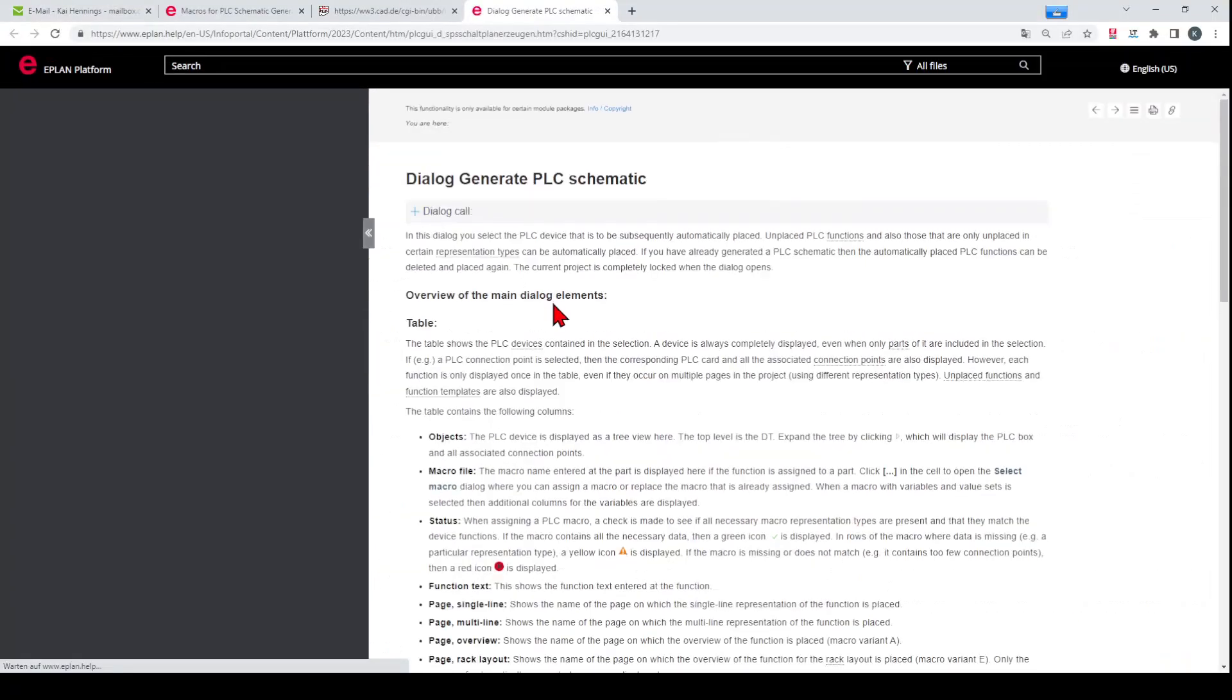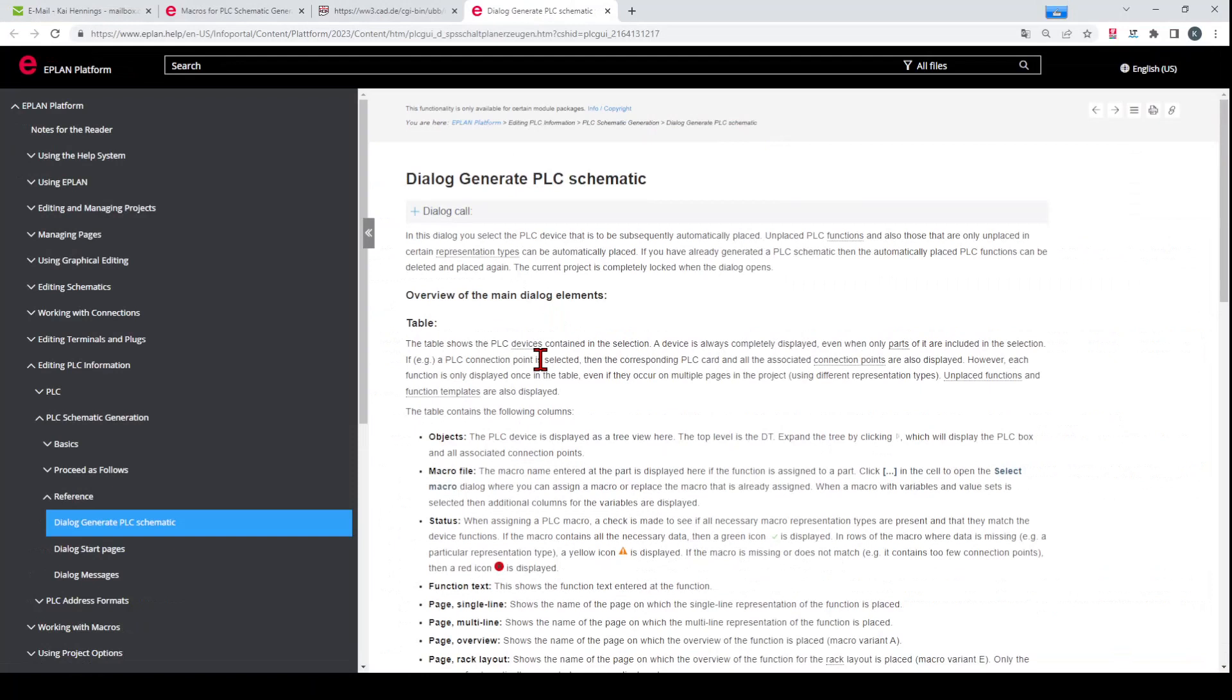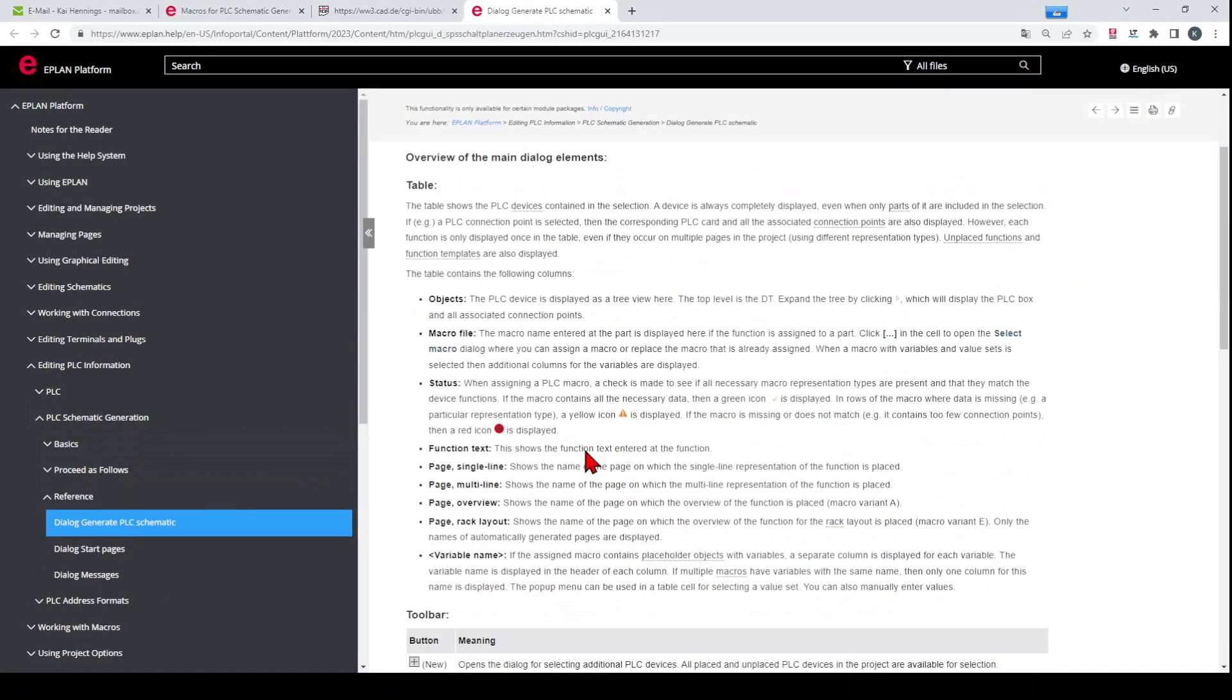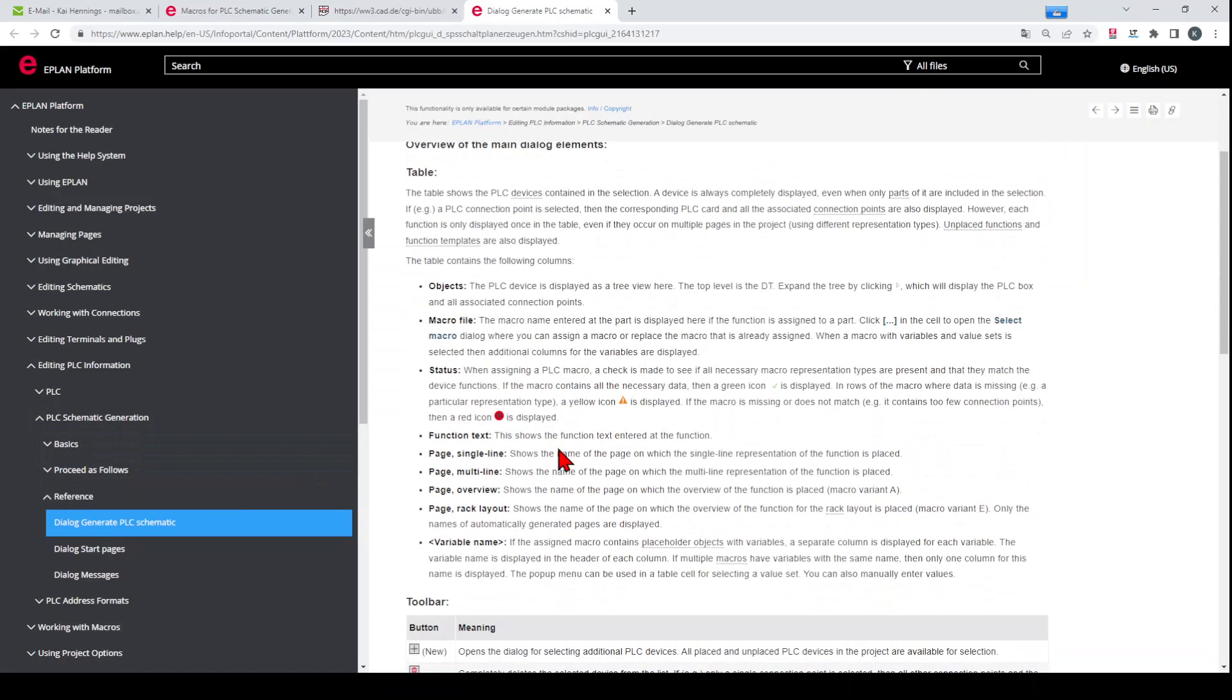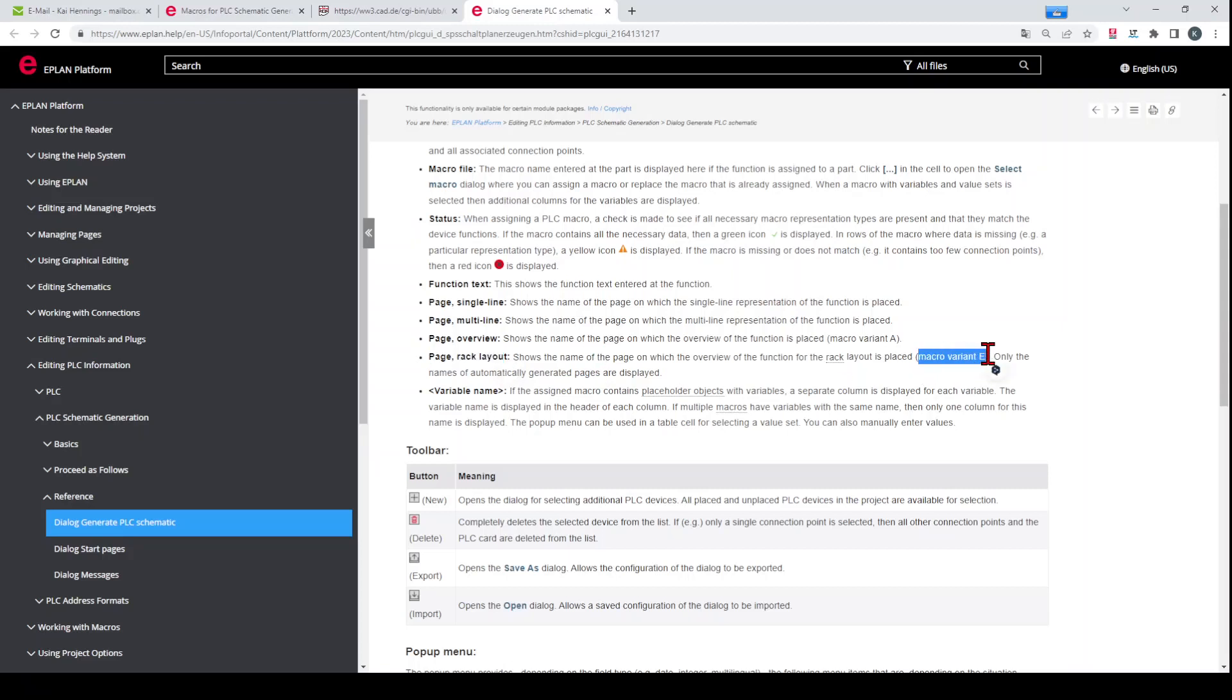The same is here for the rack layout. We can click F1. And here in the ePlan help, you can also get a lot of information about this function. And for example, when you want to generate the page rack layout, you need to have a macro and a variant E of the page type overview. So this is the requirement you need to fulfill.